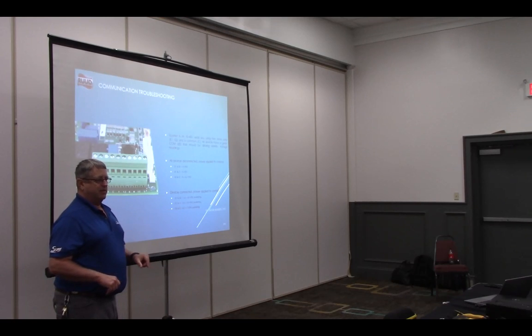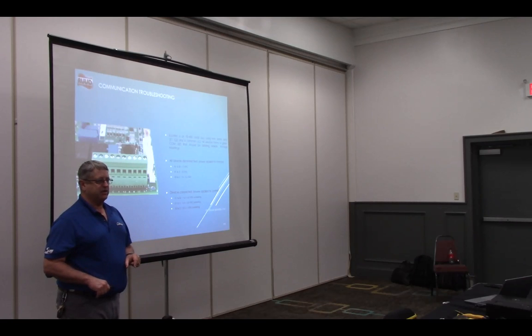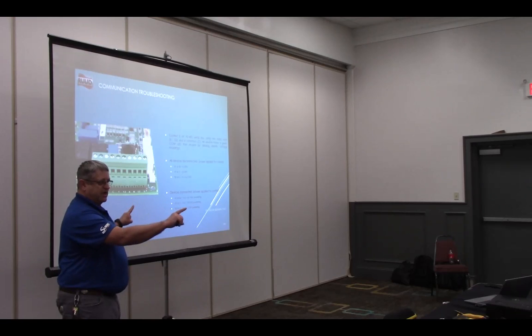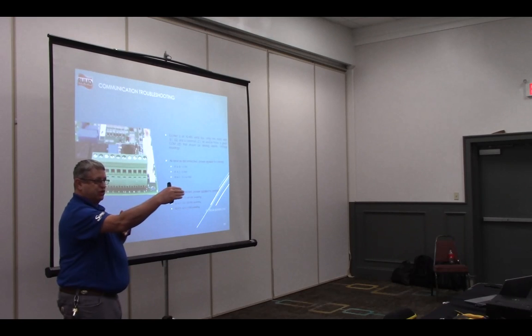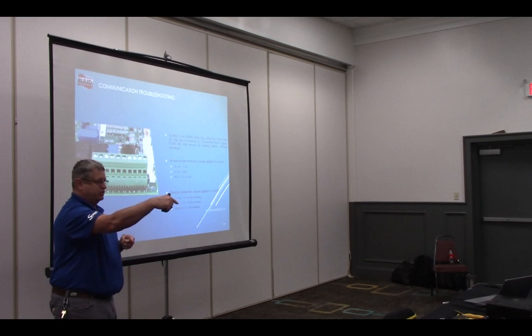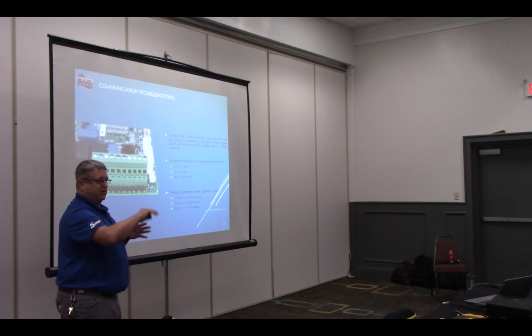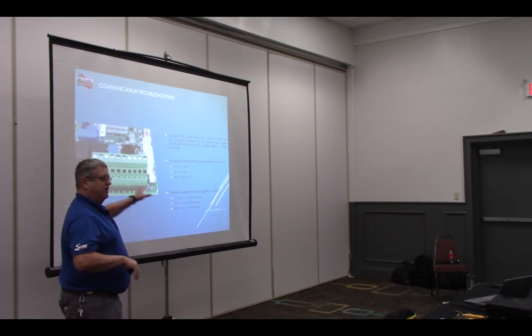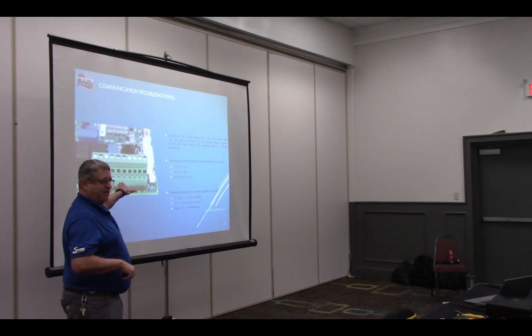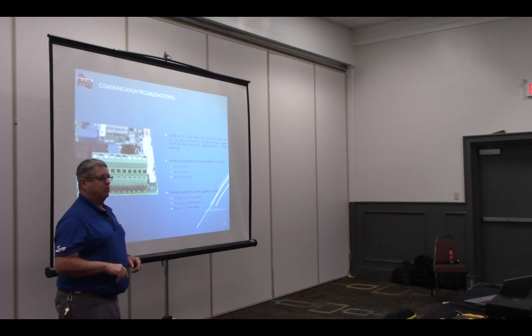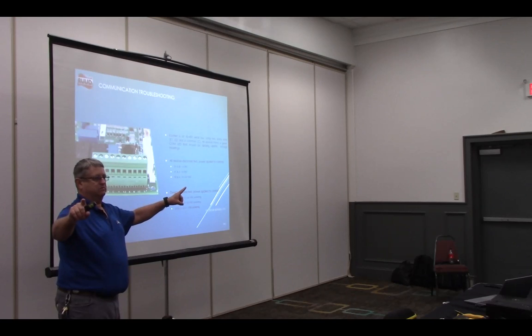If you bring it up and you don't have a communication error, where's your problem? The thermostat wire, right? Because now we just took that out of the circuit, right? We just have the short piece, brand new. If the communication error goes away, it's between there and the thermostat. If you still have the communication error, where's the problem? Between the indoor and the outdoor.